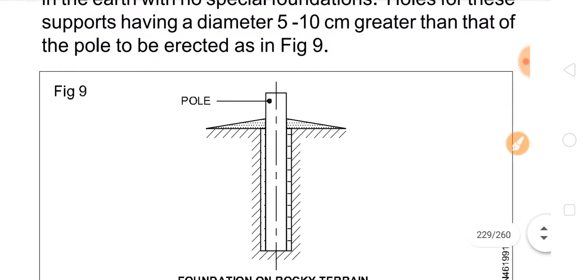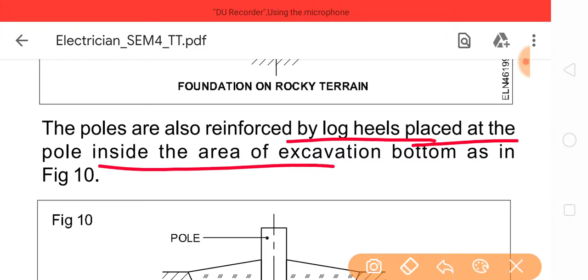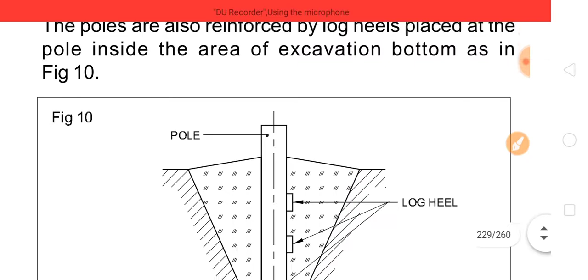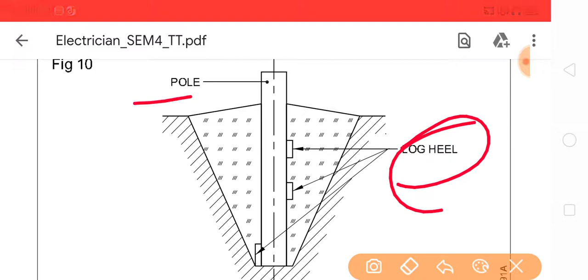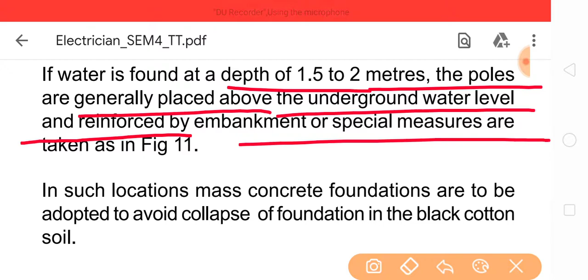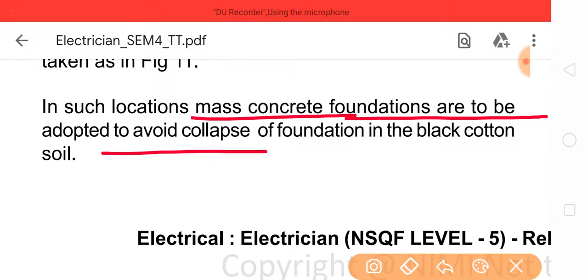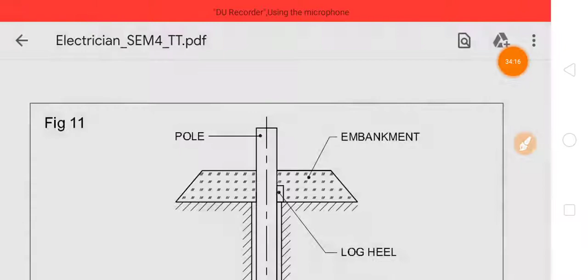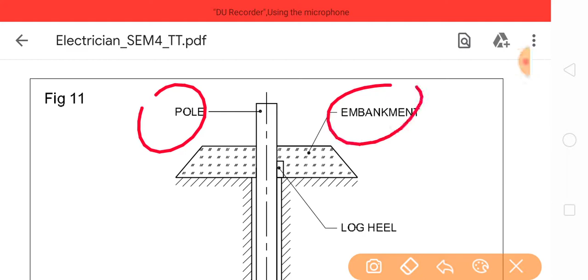This is the pole and foundation on rocky terrain. The poles are also reinforced by log heels placed at the pole inside the area of the excavation's bottom, as in picture 10. Picture 10 shows steel poles and foundation in solid ground. If water is found at a depth of 1.5 to 2 meters, the poles are generally placed above the underground water level. They are reinforced by embankment, or special measures are taken as in picture 11. In such locations, mass concrete foundations are to be adopted, and to avoid collapse of foundation in the black cotton soil. Picture 11 shows poles with embankment, log hill and foundation on clay soil.